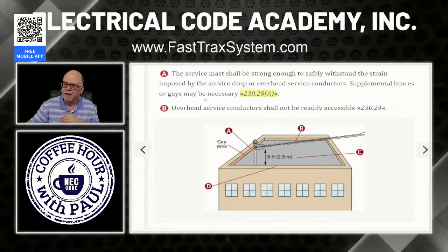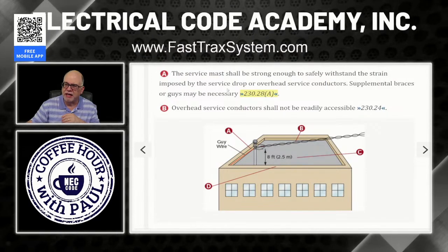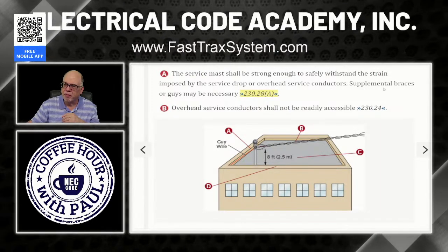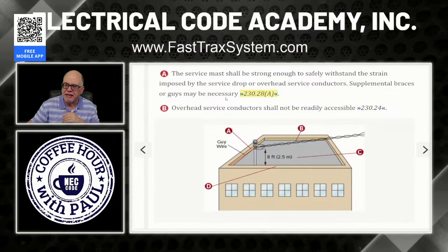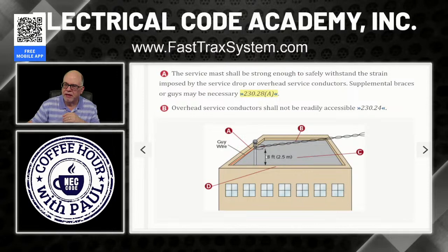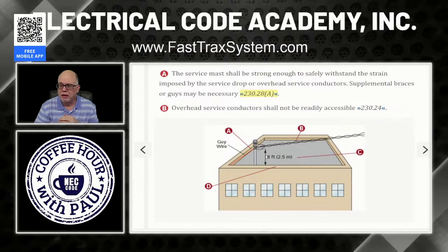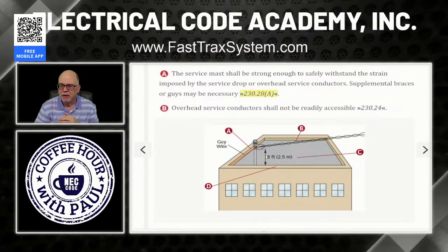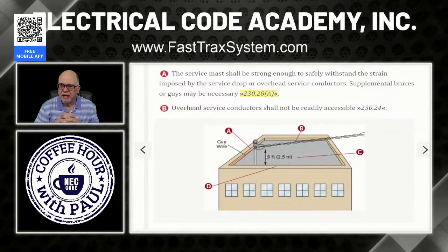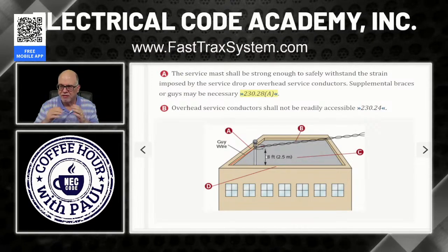All right, so here we're looking at A. It says the service mast shall be strong enough to safely withstand the strain imposed by the service drop or overhead service conductors. Supplemental braces or guy wires may be necessary. In this case, they needed to maintain the clearance above the roof, so they raised up the weatherhead on a mast, but if it's up too high, they have to make sure they put guy wires in. So we'll go look at that.